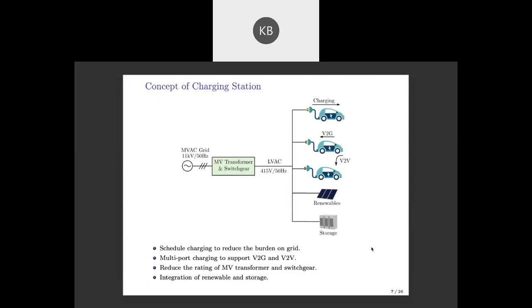If you have a few of these cars charging, it can quickly become a megawatt amount of power. So you need to connect to a medium voltage AC grid, 11 kV MVAC. You need medium voltage transformers and switch gears to bring it down to 415 volt, 50 hertz LVAC to connect your cars.